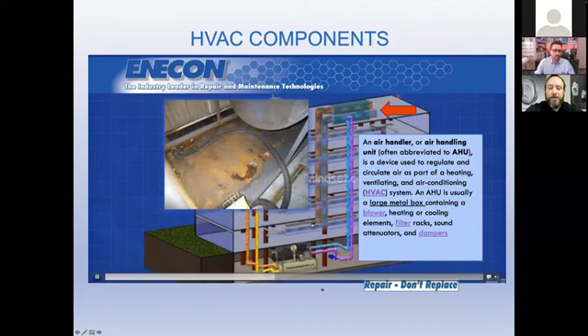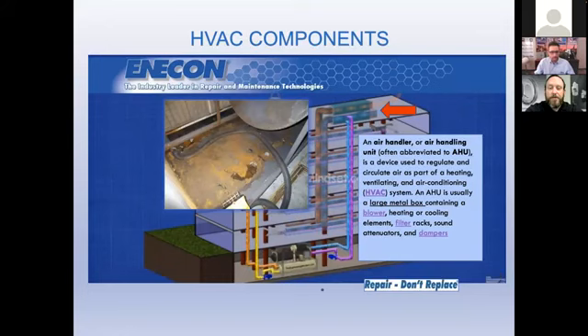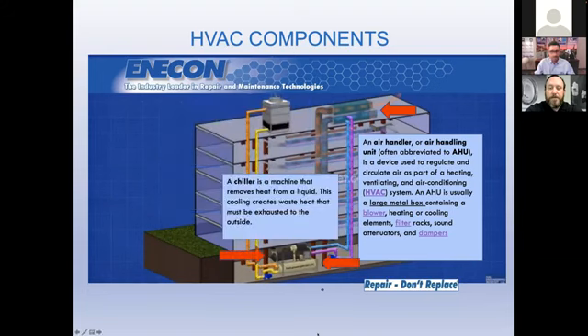Most of the problems that we see in air handlers are from the condensation coming off the coils, collecting in the pan and not properly draining out. This causes corrosion over time, and sometimes the corrosion leads to leaks from the unit itself onto the floor in the building where it's not wanted. These types of issues are very easily resolved and will be a focus in a future segment in our HVAC corrosion webinar series. Next in line is the chiller in the system. It's typically comprised of an evaporator and a condenser, and this will be the main focus of this webinar today.